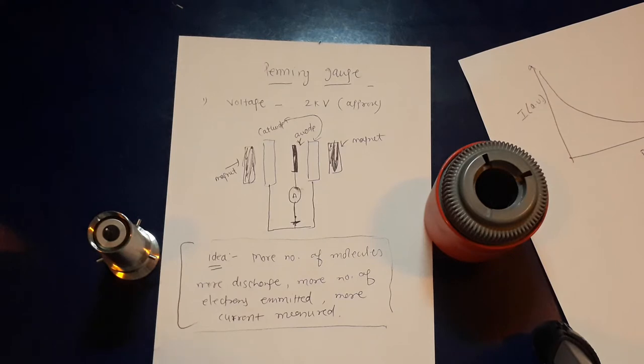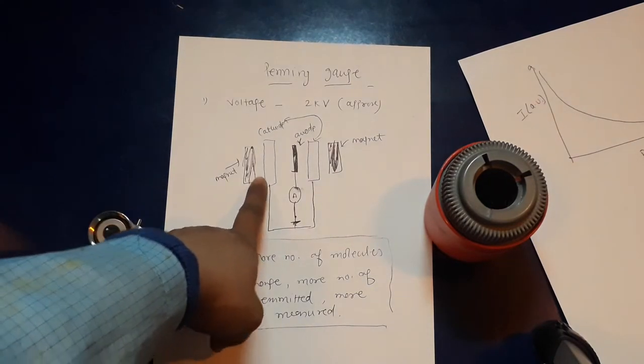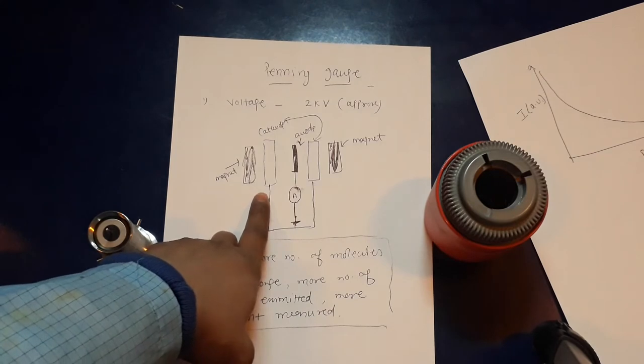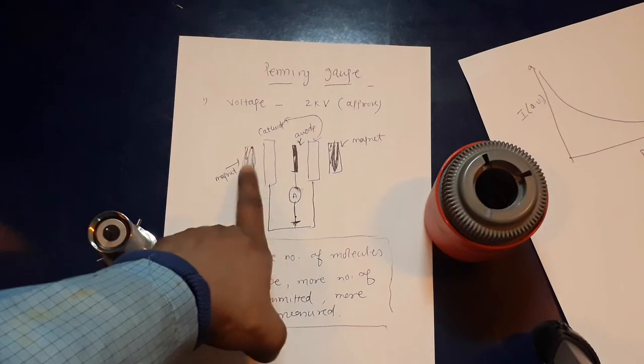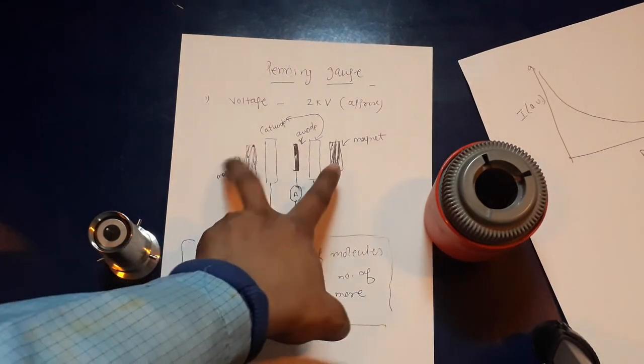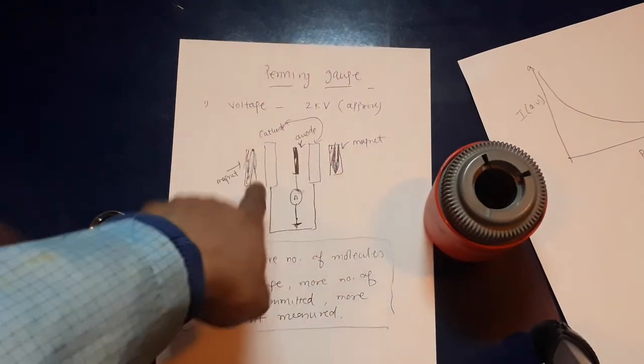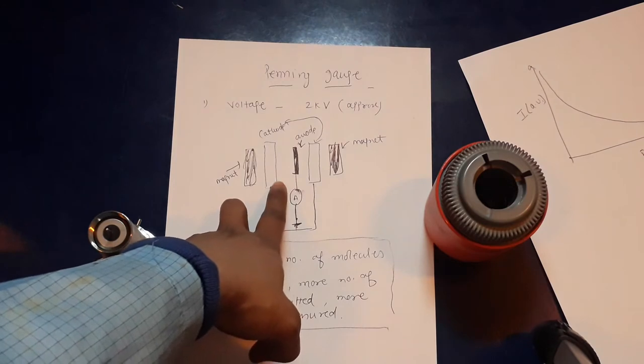What is happening here is there is a cathode where you apply very, very high voltage and there is an anode. These pieces are inside a permanent magnet. So when you apply a very high voltage, there will be some gas molecules and the discharge will happen.